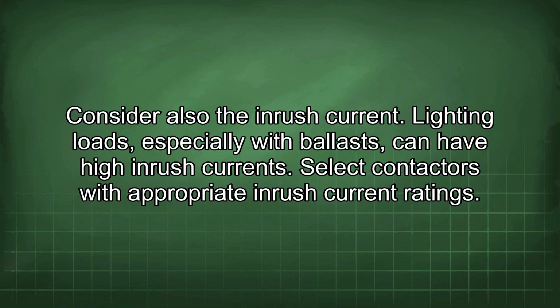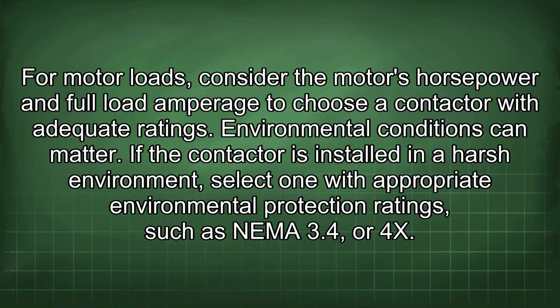Consider also the inrush current. Lighting loads, especially with ballast, can have high inrush currents. Select contactors with appropriate inrush current ratings. For motor loads, consider the motor's horsepower and full load amperage to choose a contactor with adequate ratings.